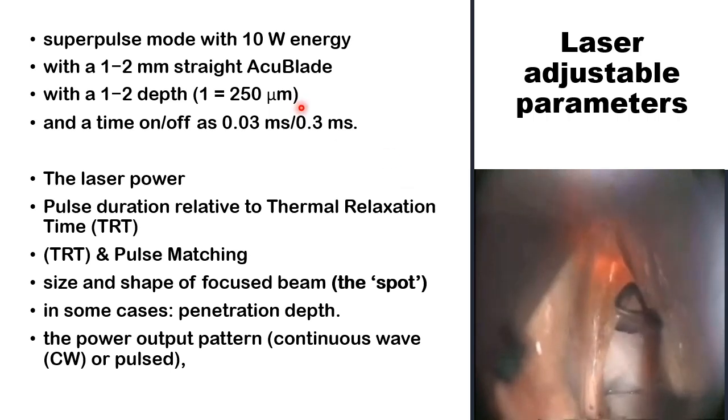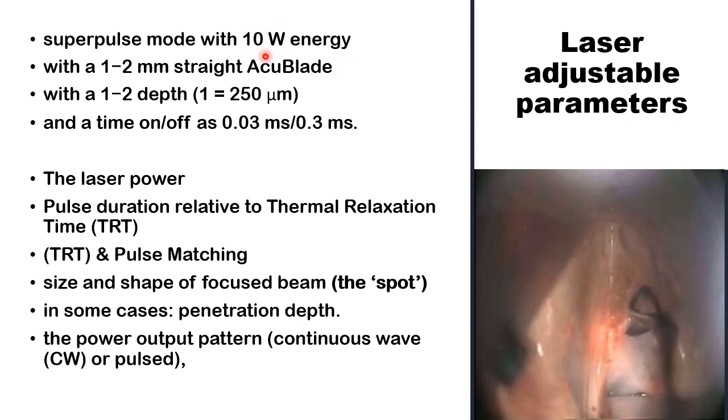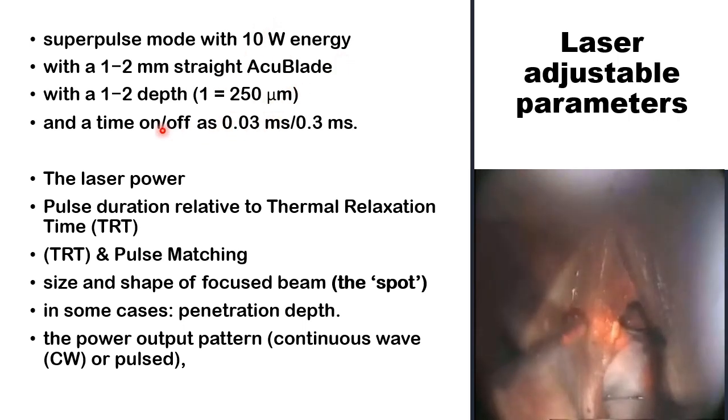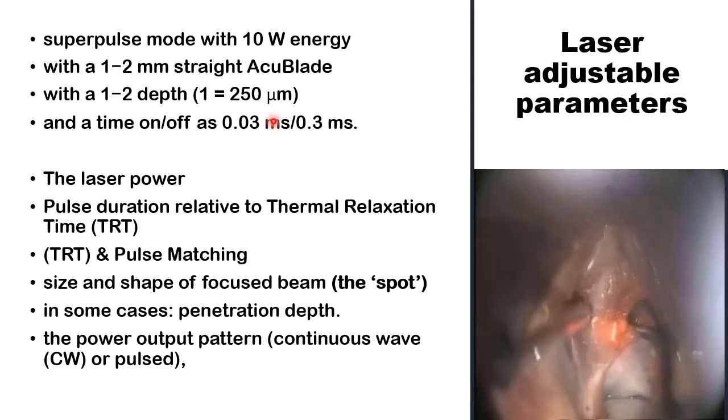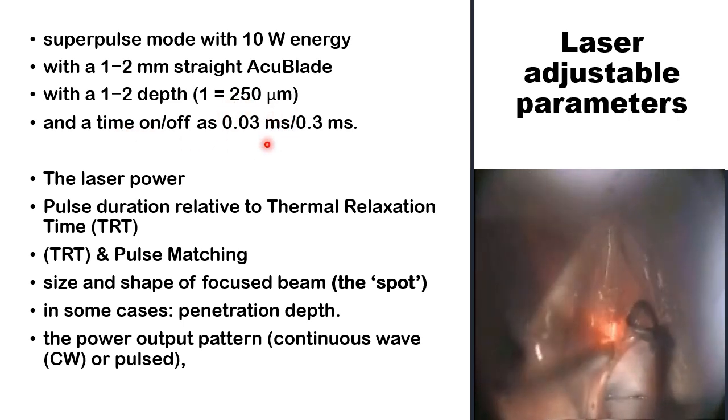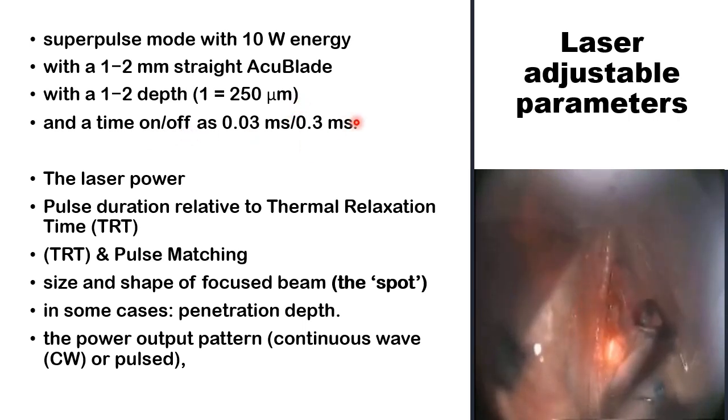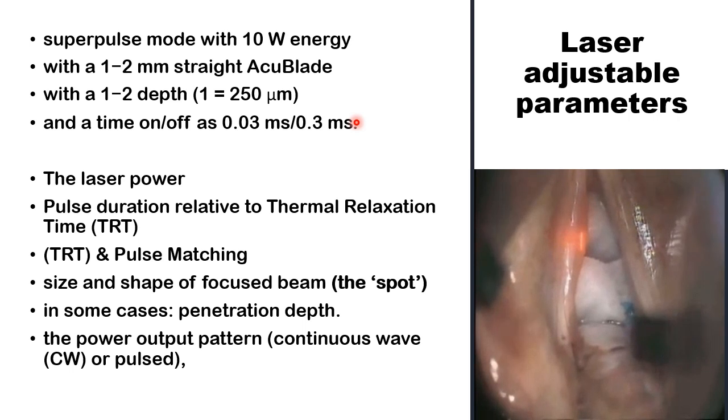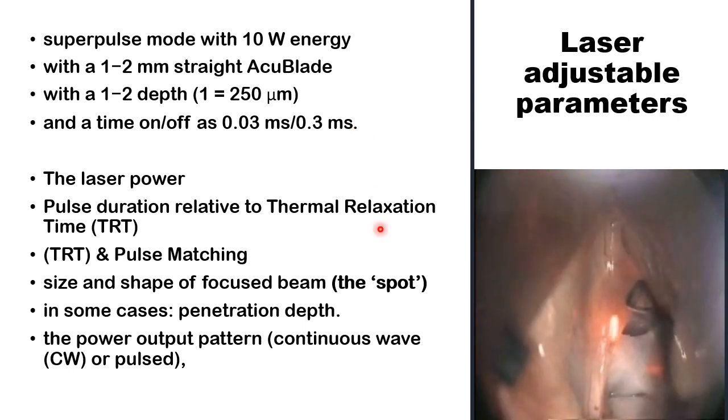But there is this other aspect now, the time through which this energy would be distributed over this focus area. Not only the time when the energy is on, which should be very brief, but also the time when the energy is off to allow for the cooling of the tissues to avoid charring. And this we're going to discuss over the next few slides.